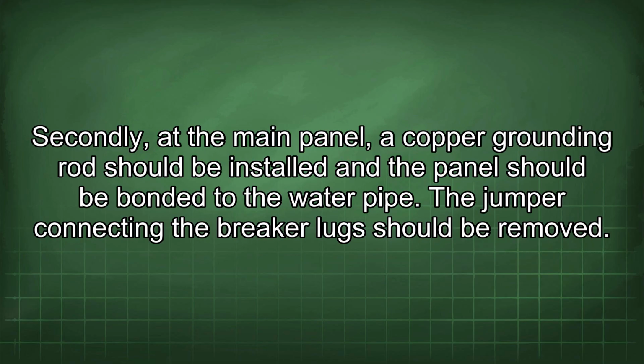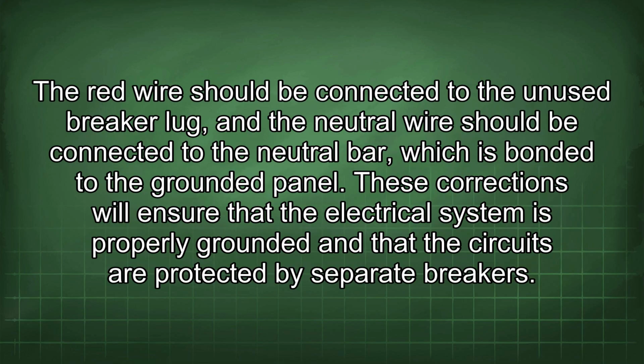Secondly, at the main panel, a copper grounding rod should be installed and the panel should be bonded to the water pipe. The jumper connecting the breaker lug should be removed. The red wire should be connected to the unused breaker lug, and the neutral wire should be connected to the neutral bar, which is bonded to the grounded panel. These corrections will ensure that the electrical system is properly grounded and that the circuits are protected by separate breakers.